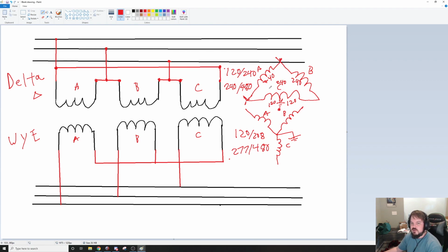So if they're using 120 volt or single phase loads, they'll have breaker, breaker, skip, breaker, breaker, skip, because they'll have 120, 120, and then 208. And 208 is not a useful voltage for anything, so they skip that breaker. Or they could use a 2-pole breaker and get 240. A lot of them will strategically place the 2-pole breakers in the panel so that you get 240 in different spots.